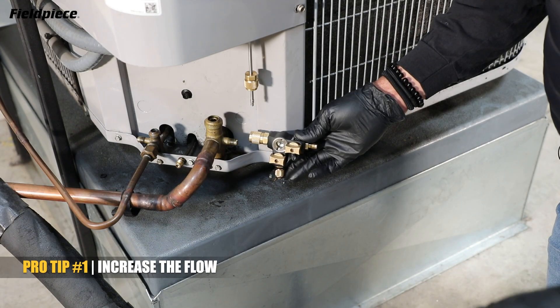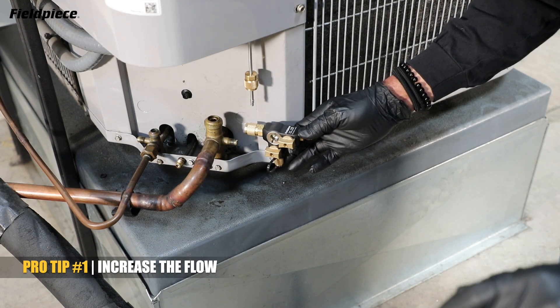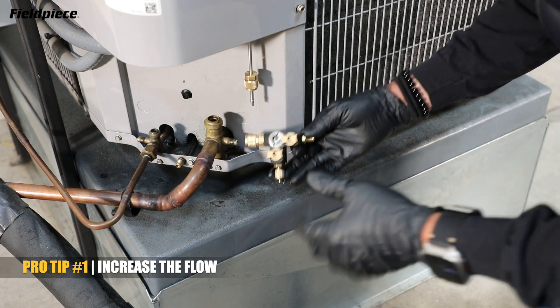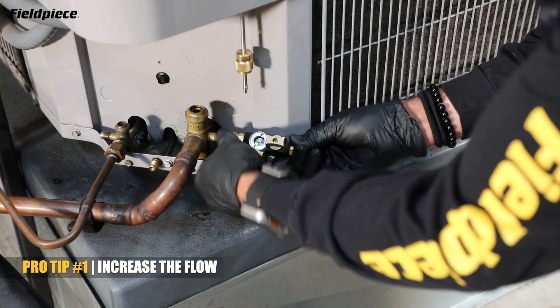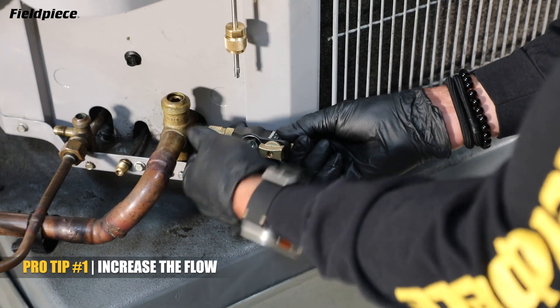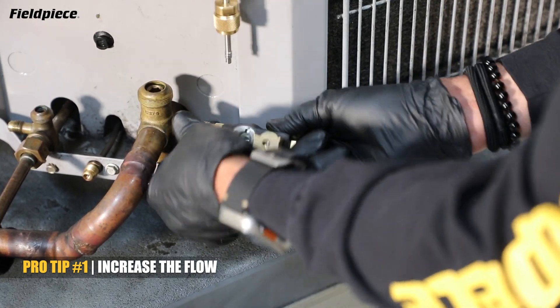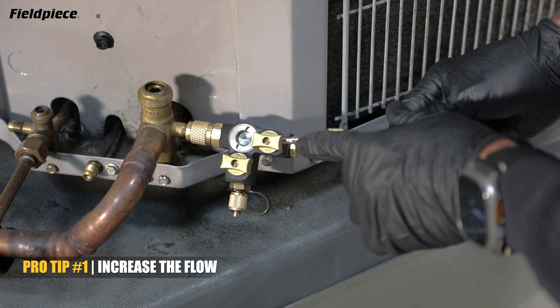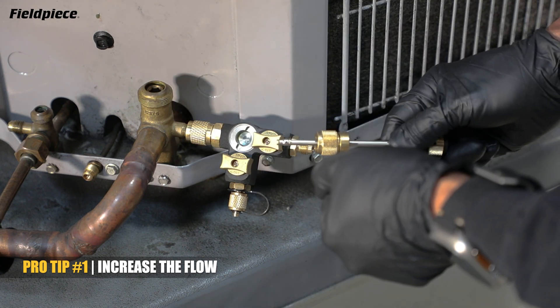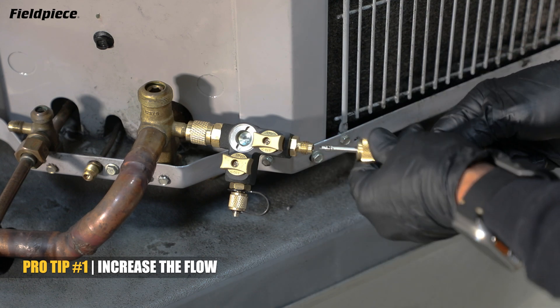The first way to do that is remove valve cores from the service ports using a valve core removal tool. The Fieldpiece VC2G makes this job even easier and faster. First you connect your core tool onto the service port of your system. The VC2G has an enhanced grabber so that it will more securely grab onto the valve core and not drop it without having to make adjustments to the tip.